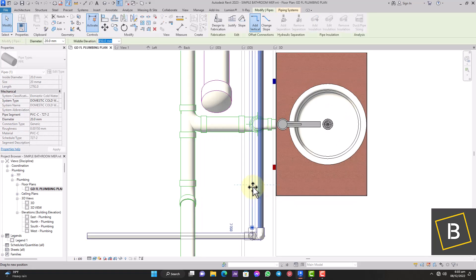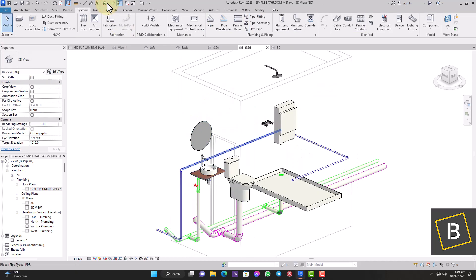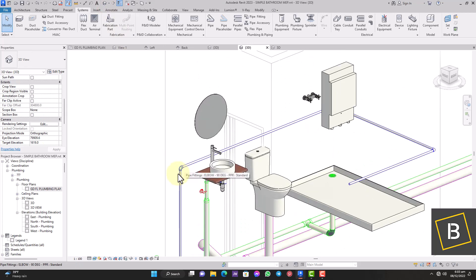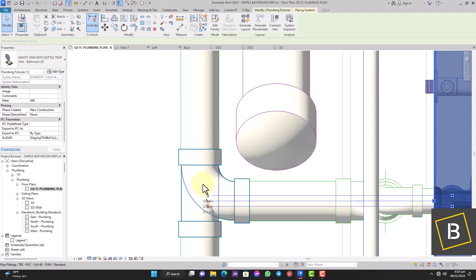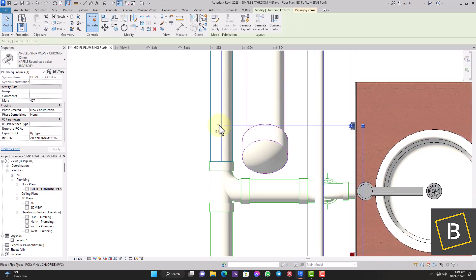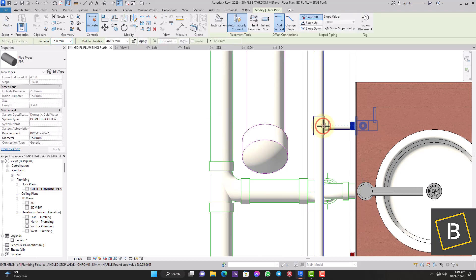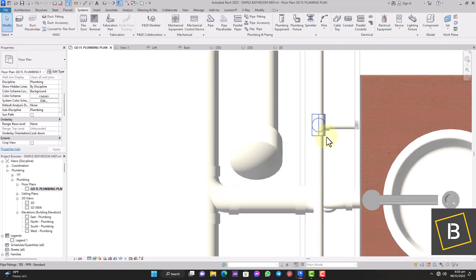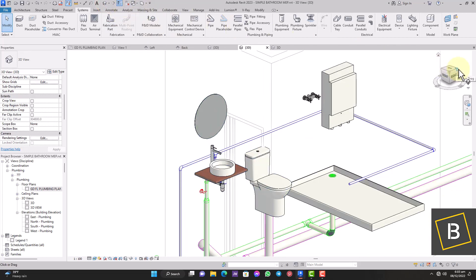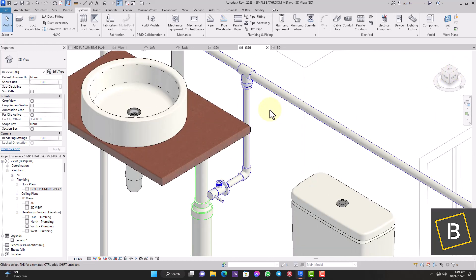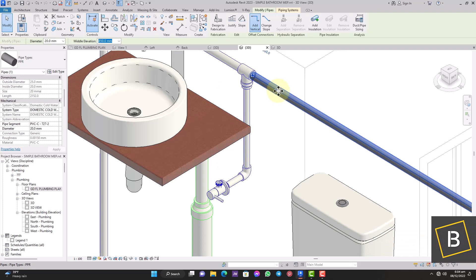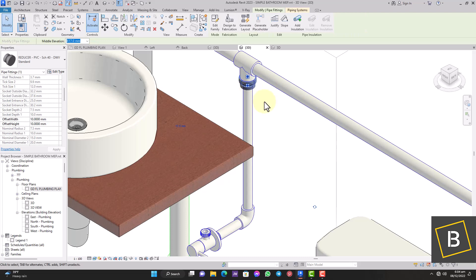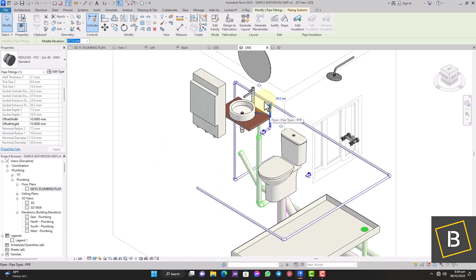The cold water pipe is in place — let's check that in 3D. Now we need to connect the fixtures to the cold water supply line. The first fixture is the basin. I'm going to find the angle valve right underneath the basin, click on the connector to create the pipe, and join it. Revit automatically created the basin connection to the cold water line. The basin piping is 15mm and the main line is 20mm, so Revit automatically creates a reducer — no need to worry about that.